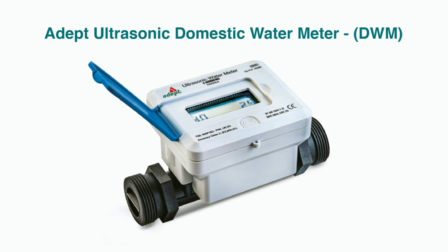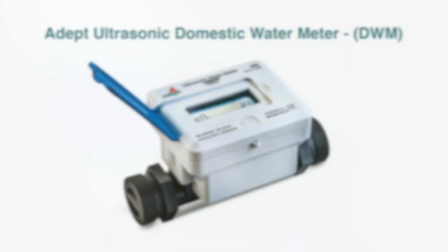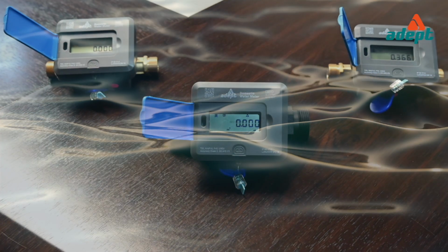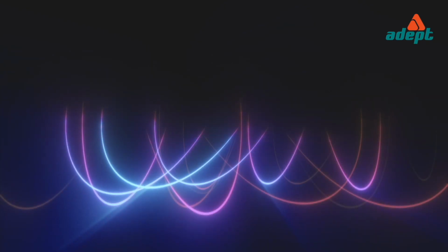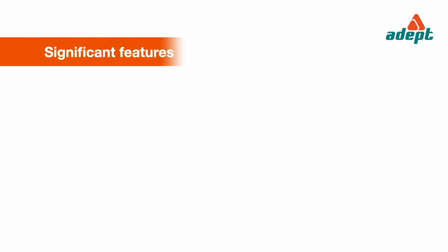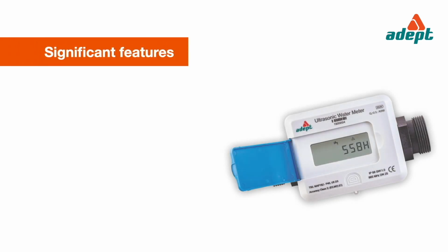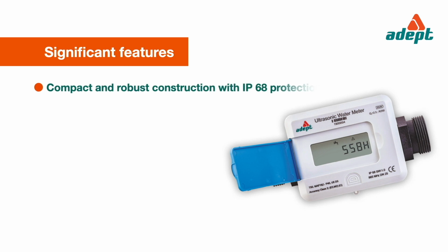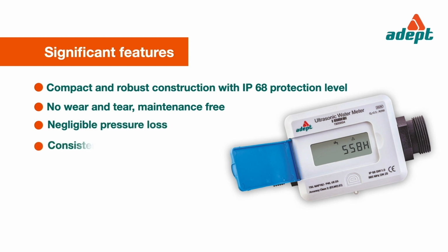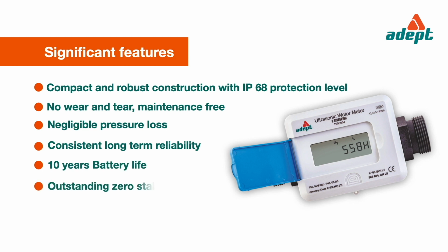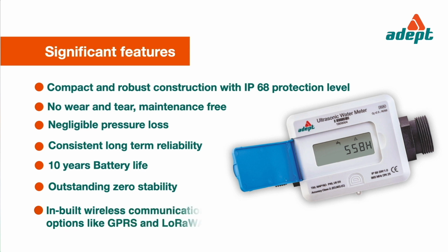Adept ultrasonic domestic water meters (DWM) are used to measure the flow rate of water. They function on the basis of the transit time method of ultrasonic waves and can measure bidirectional flow. Significant features of Adept's DWM are compact and robust construction with IP68 protection level, no wear and tear, maintenance free, negligible pressure loss, consistent long-term reliability, 10 years battery life, outstanding zero stability, inbuilt wireless communication with options like GPRS and LoRaWAN.